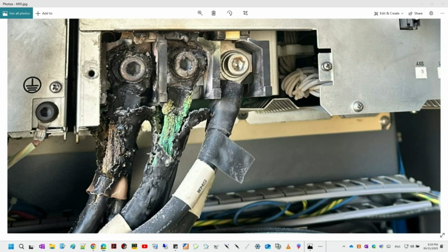How so? Well, frequently disturbing connections, retorquing them when they might be perfectly stable, can potentially introduce new issues or loosen things that were fine. Okay. Don't fix what isn't broken, potentially. Sort of. So a more, let's say, intelligent approach was proposed and agreed upon, basing the connection checks on machine usage, not just the calendar. Okay, how would that work? Specifically, performing these checks every 2,000 operating hours using the machine's own embedded hour counter. That makes a lot of sense, tying frequency to actual workload and vibration cycles, not just time passing. That's a crucial takeaway. Exactly.